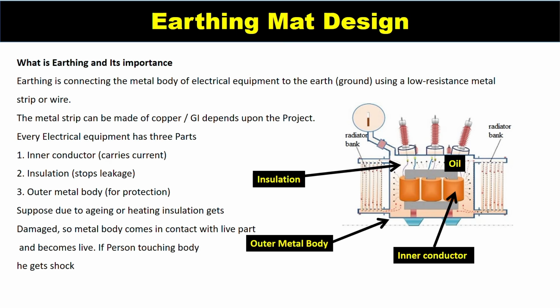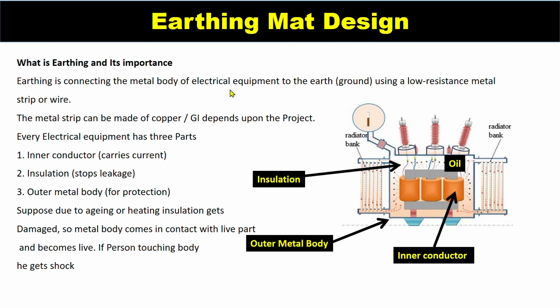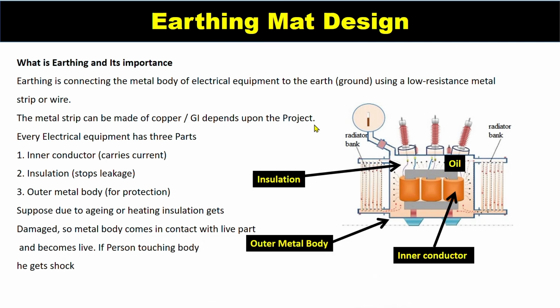First of all, we should know what earthing is and what its importance is. Earthing is connecting the metal body of an electrical equipment to the earth using a low resistance metal strip or a wire. Here I have said the metal body. You can also say earthing is connecting the metal body and the neutral of the electrical equipment to the earth using a low resistance metal strip or wire. The metal strip can be made of copper or galvanized iron, depending upon the project.